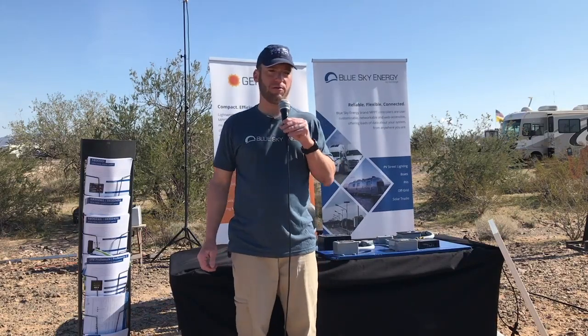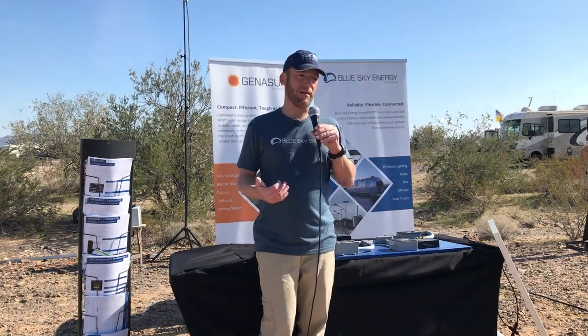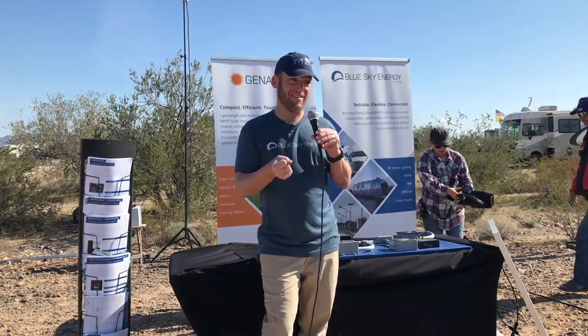So difficult to troubleshoot. Basically what you do to troubleshoot it is look at the voltage and current. Mostly the current is what tells you the most. So for example, you check the short circuit current with the wires disconnected.